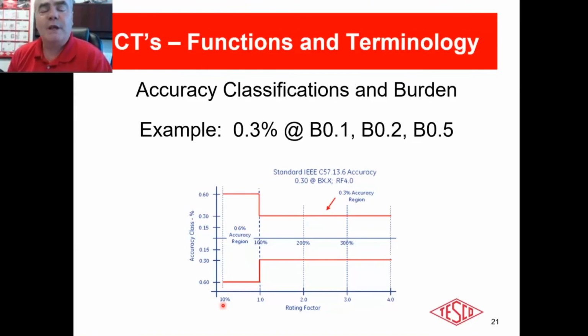But a more prevalent issue is, I only know of one utility that is just now beginning a program where they're actively going out and updating transformer rated sites with new transformers based on the new usage. The classic way of doing it, the way the overwhelming majority of installations in North America are set, I may have set the building I'm in, is a pretty old building. The CTs here may have been set 20, 30, 40, 50 or more years ago. Maybe the service, I know the service was last updated in 2004. So these transformers have maybe been here for 16 years, these instrument transformers on this building.